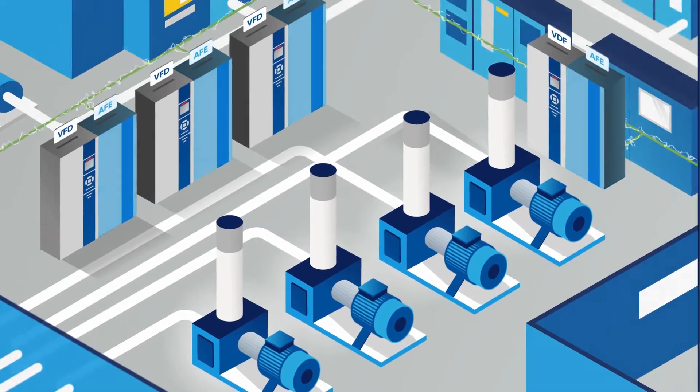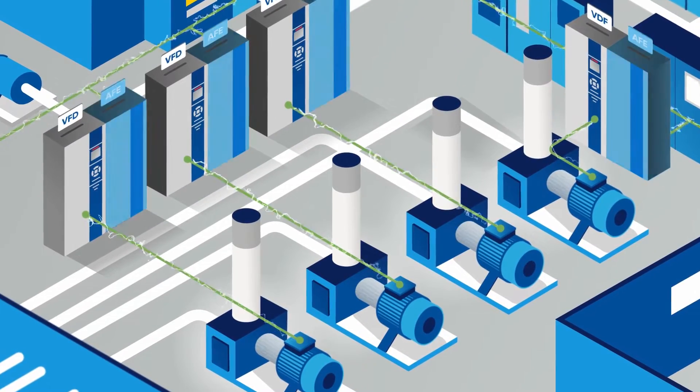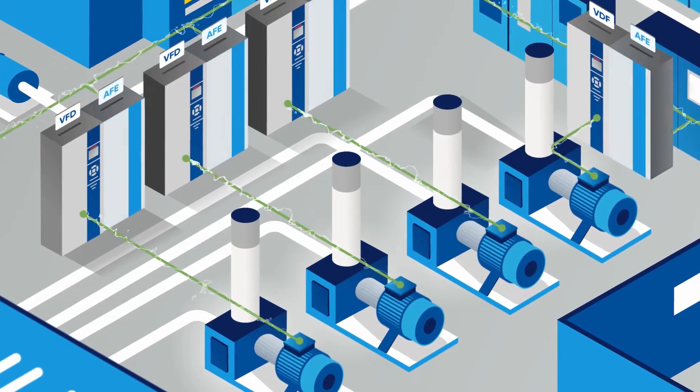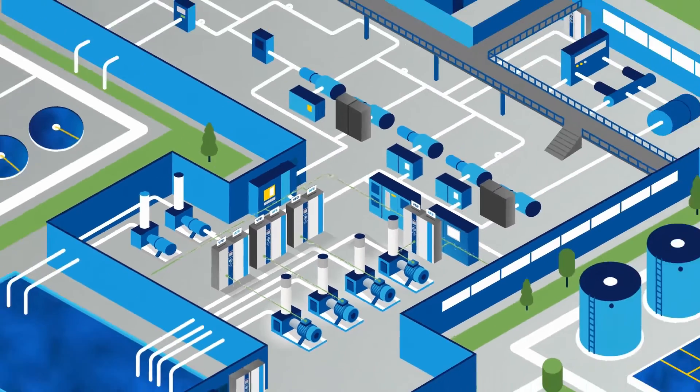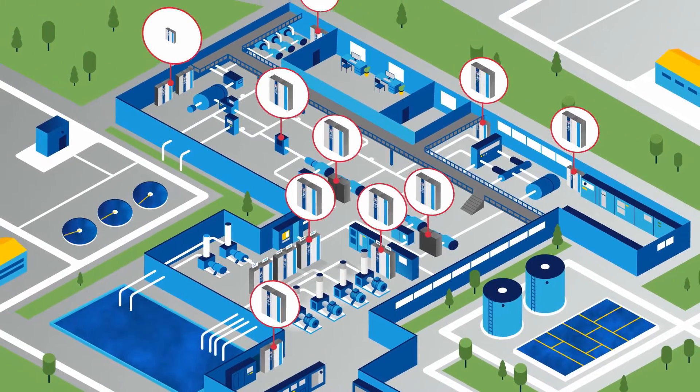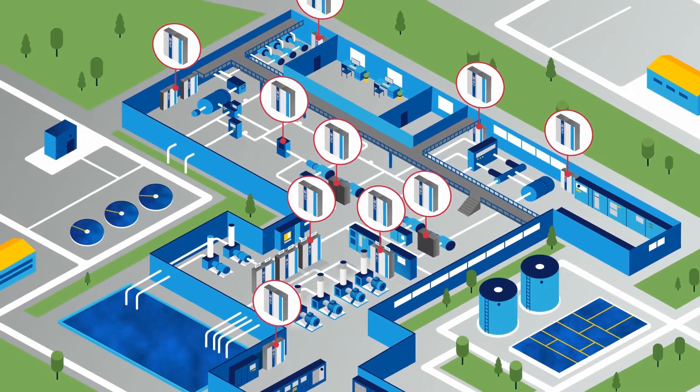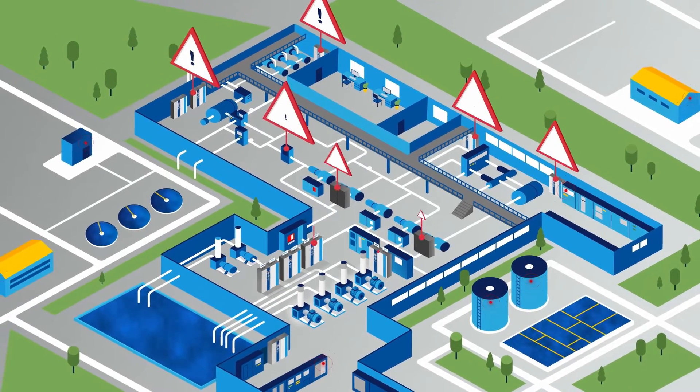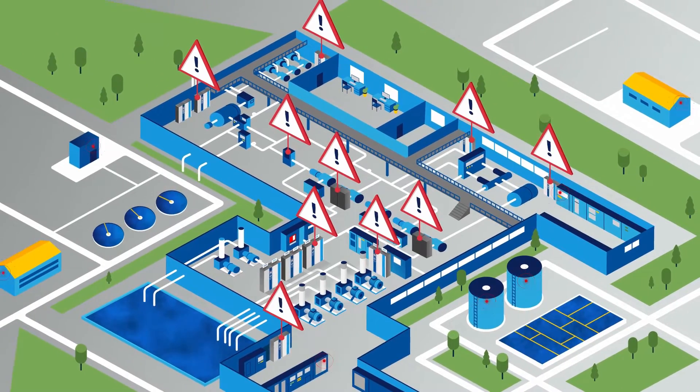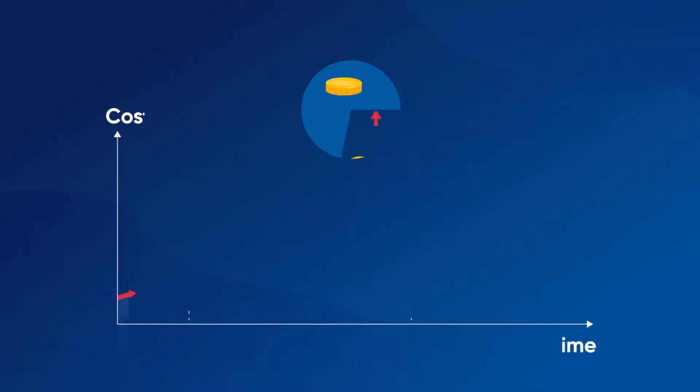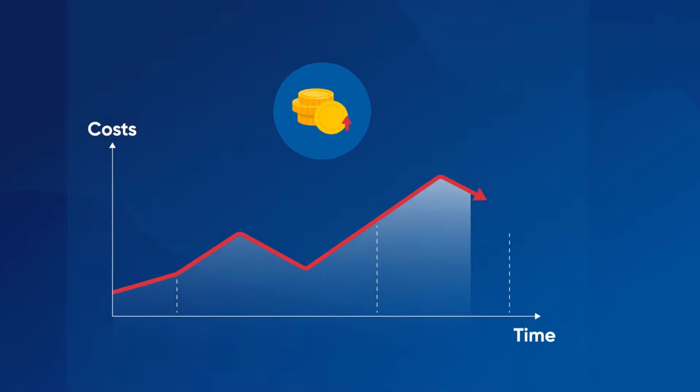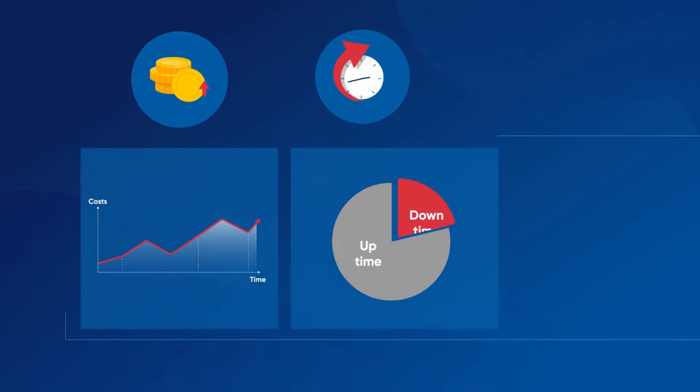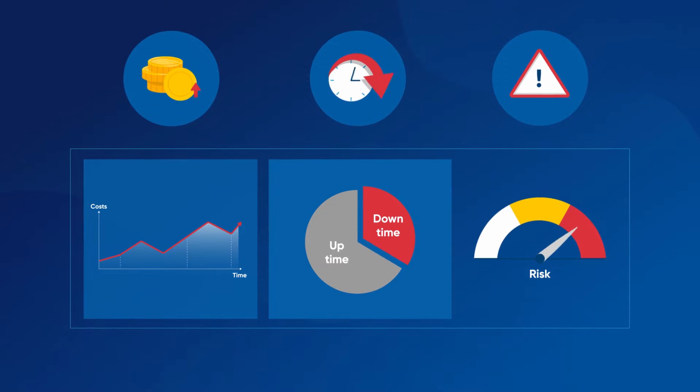When using an AFE, individual mounting on each motor is required. This requires a more complex installation and involves larger amounts of components, which leads to an increased risk of hardware failure. This in turn raises both costs, downtime, and adds risk to the operations.